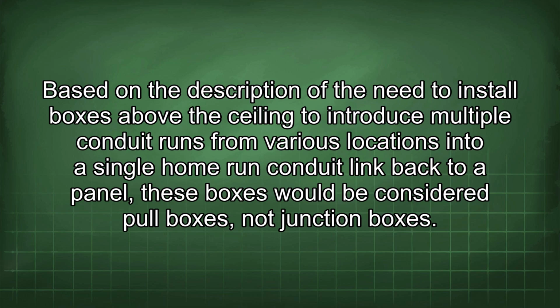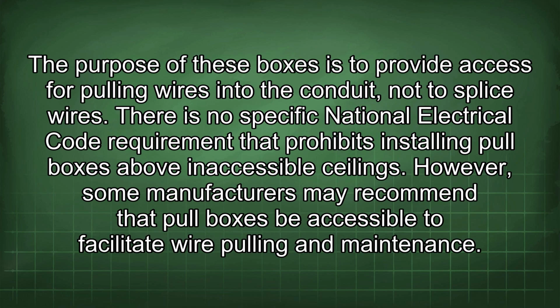Based on the description of the need to install boxes above the ceiling to introduce multiple conduit runs from various locations into a single home run conduit linked back to a panel, these boxes would be considered pull boxes, not junction boxes. The purpose of these boxes is to provide access for pulling wires into the conduit, not to splice wires. There is no specific national electrical code requirement that prohibits installing pull boxes above inaccessible ceilings. However, some manufacturers may recommend that pull boxes be accessible to facilitate wire pulling and maintenance.